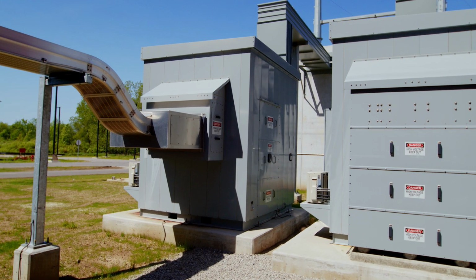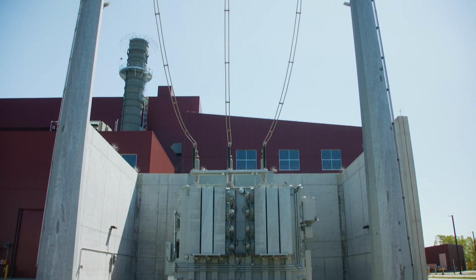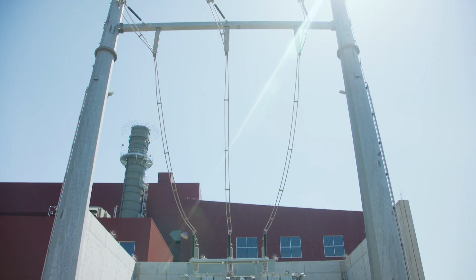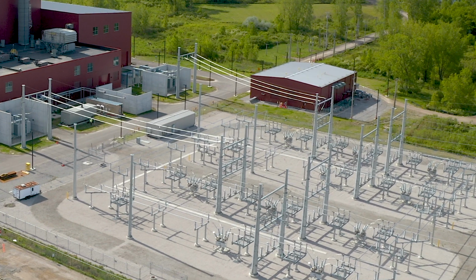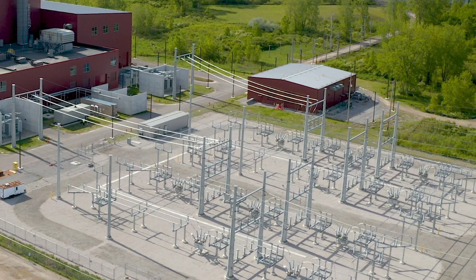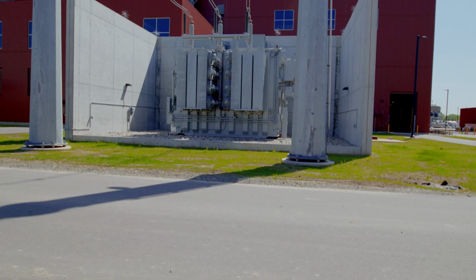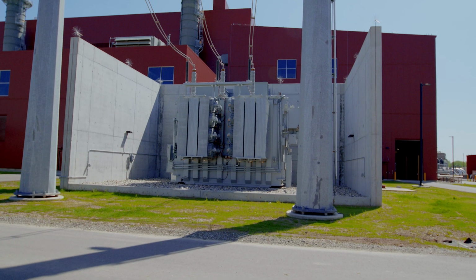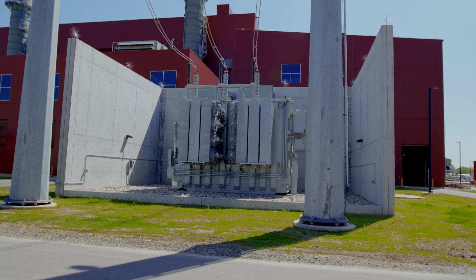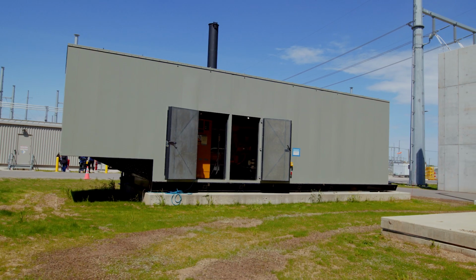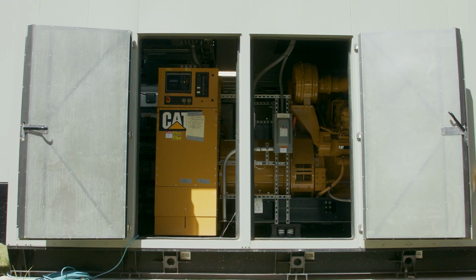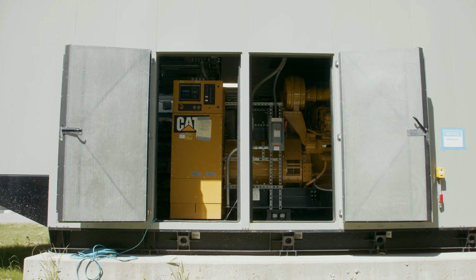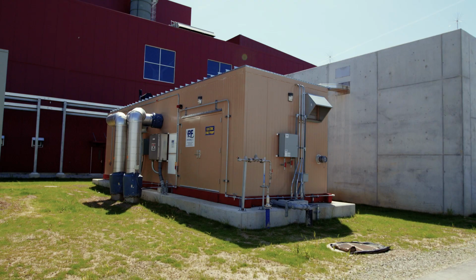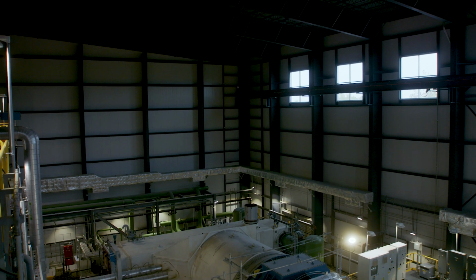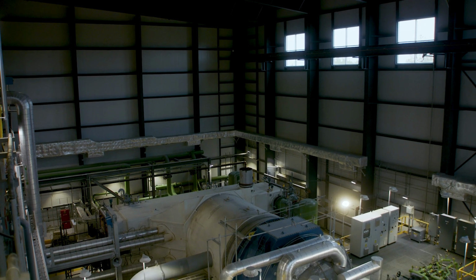All this power goes out on the grid. DEP feeds 13.2 kilovolts out to step-up transformers that takes it up to 138 kilovolts. This power is also backfed and stepped down in order to provide power to run the plant itself. Just in case, a 0.5 megawatt generator is also on standby to power emergency lighting and fire pumps in the event of power interruption.